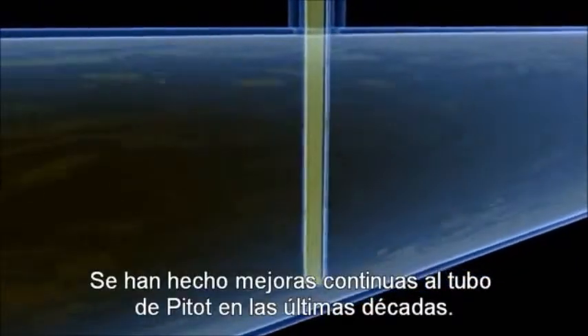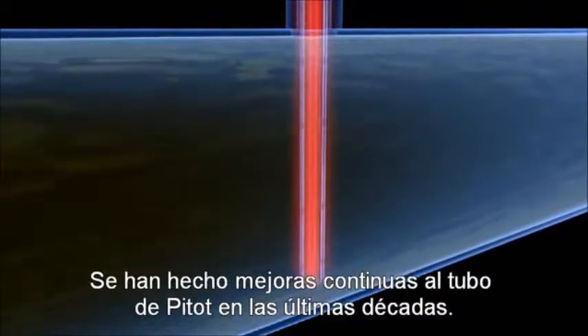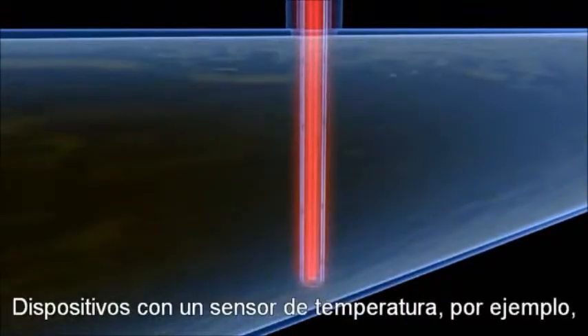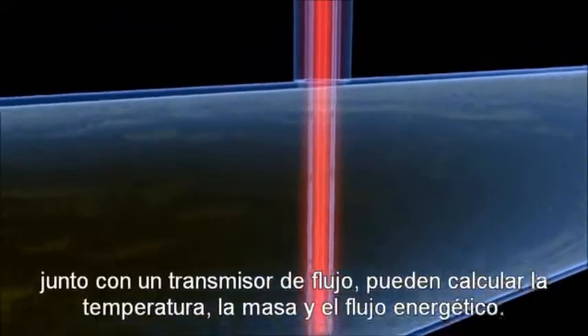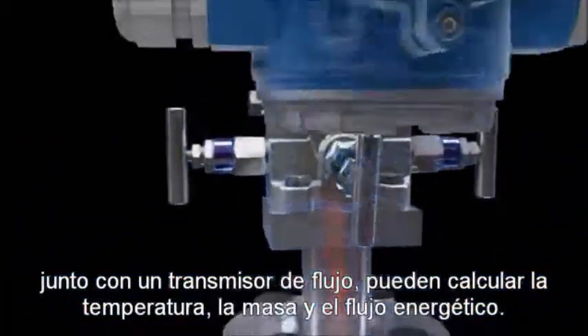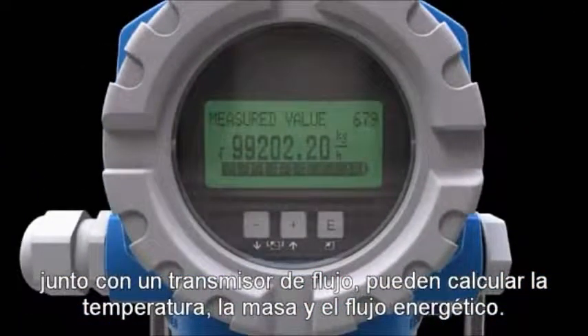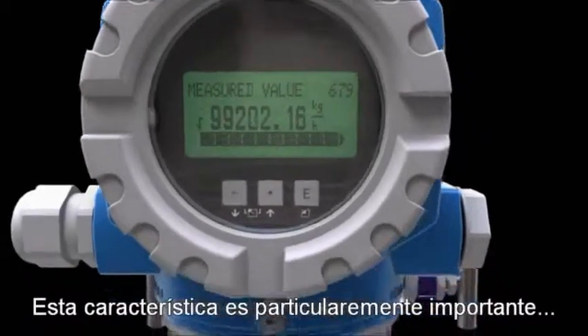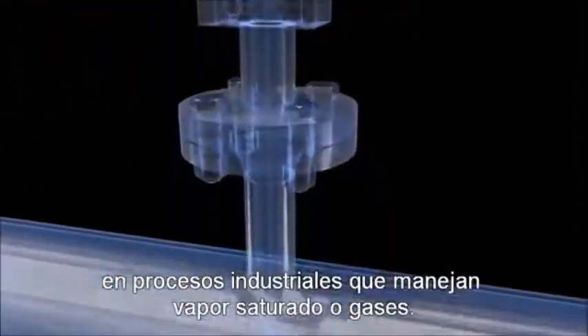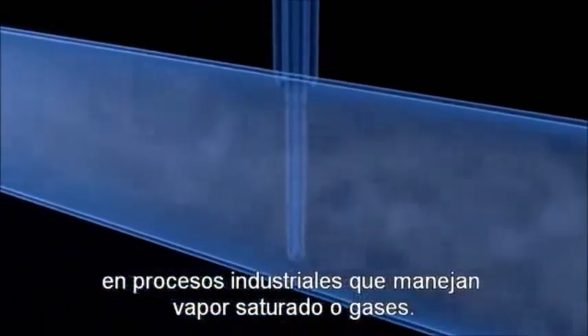Continuous improvements have been made to Pitot tubes over the past decades. Devices with a built-in temperature sensor, for example, together with a flow computer, can also calculate temperature-dependent mass and energy flows. This feature is particularly important in industrial processes involving saturated steam or gases.